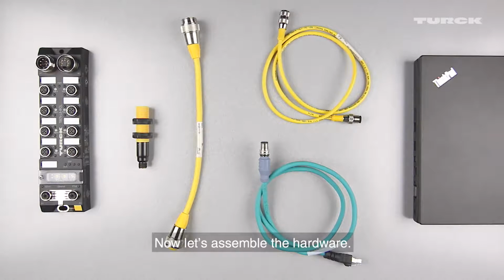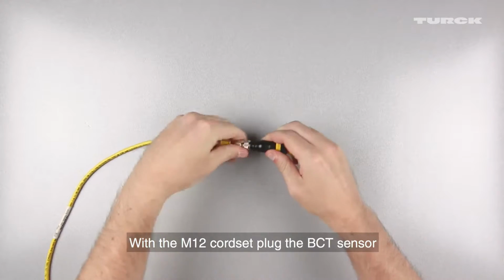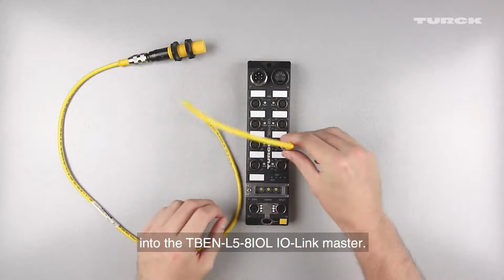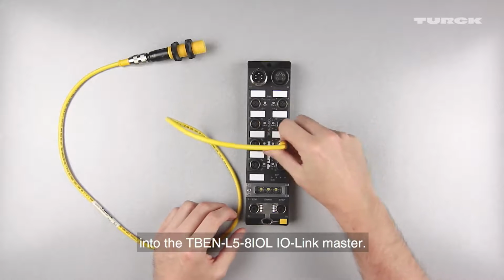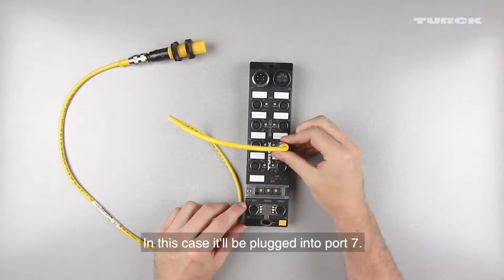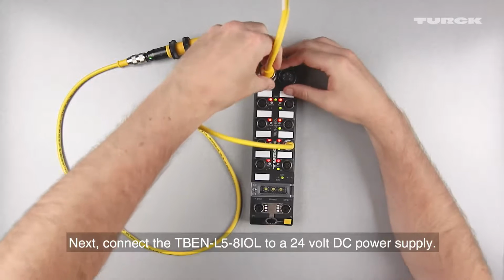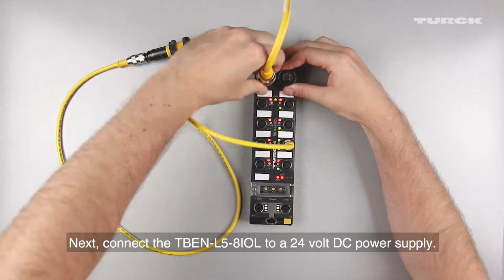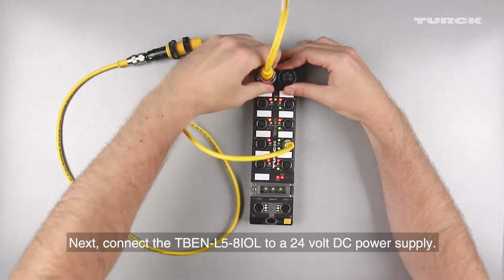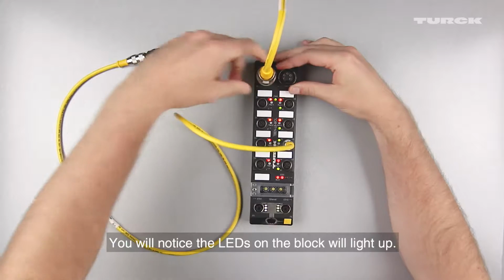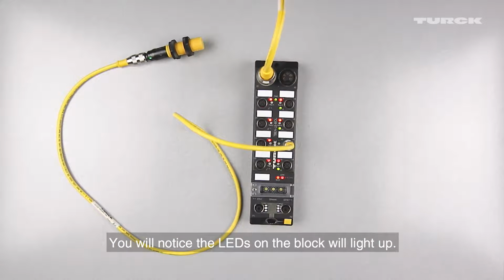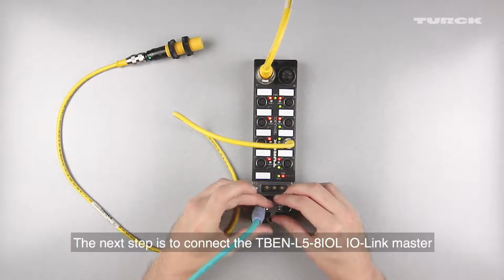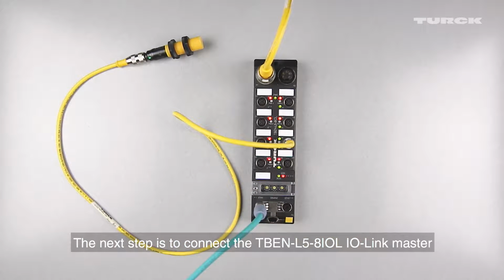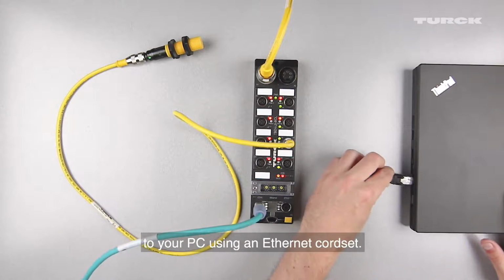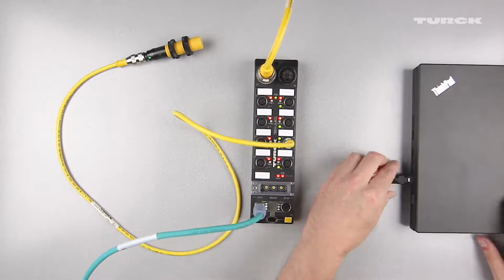Now let's assemble the hardware. With the M12 cordset, plug the BCT sensor into the TBEN-L5-8 IOL IO-Link master. In this case, it will be plugged into port 7. Next, connect the TBEN-L5-8 IOL to a 24-volt DC power supply. You will notice the LEDs on the block will light up. The next step is to connect the TBEN-L5-8 IOL IO-Link master to your PC using an Ethernet cordset.